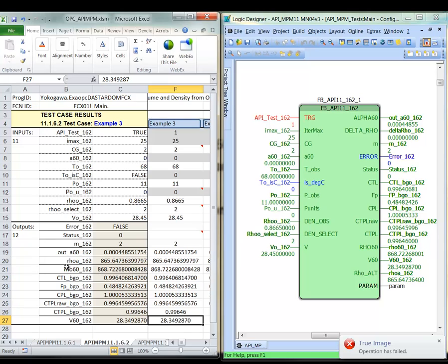So shortcut here, you can always look at them one by one, but I'm going to try to speed this up in this video just by having you direct your attention to the density at base conditions, which is 60 degrees Fahrenheit, and then volume at base conditions, which is 60 degrees Fahrenheit. If these two match the published results, then we know that the correction factors are correct. Otherwise, there's no way we could get that result, right?